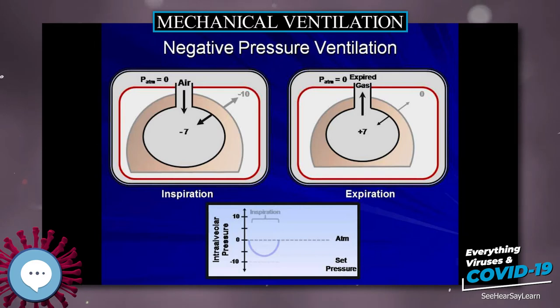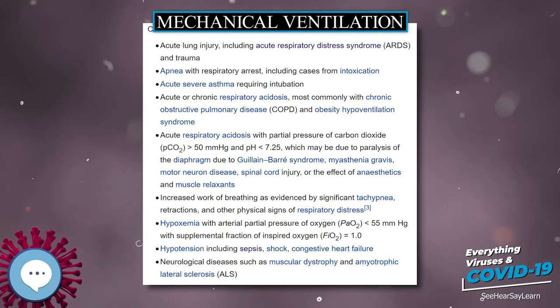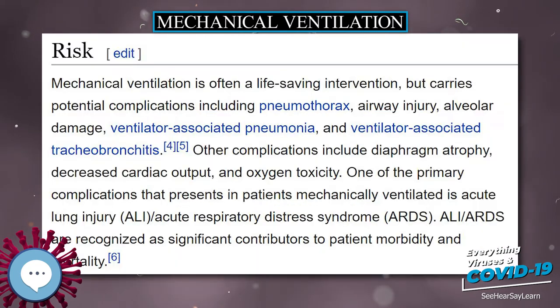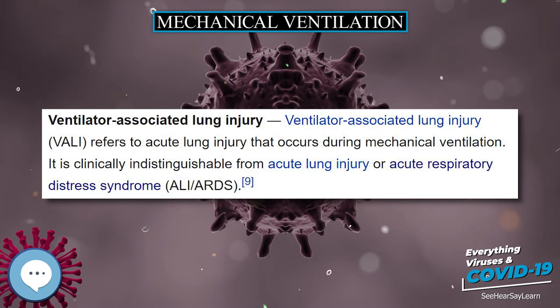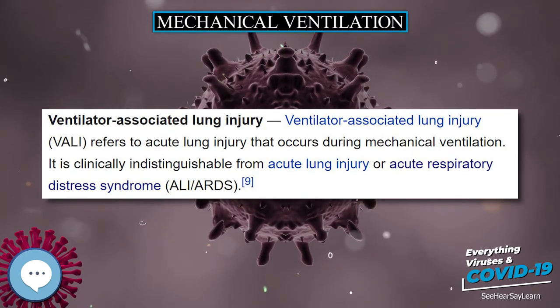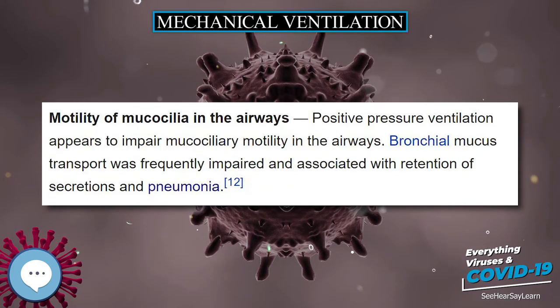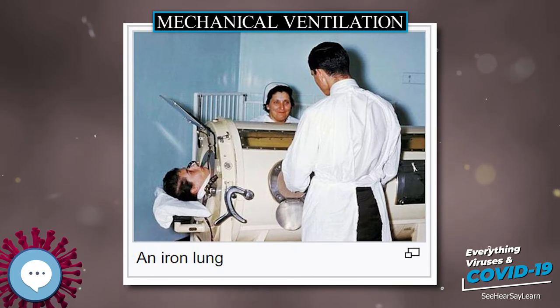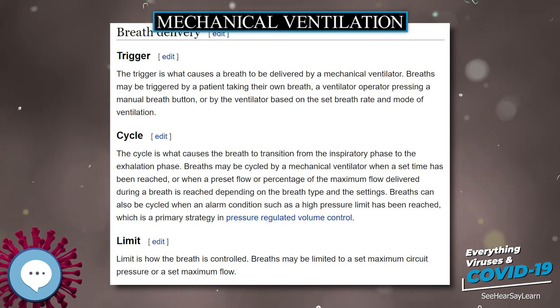While the exchange of oxygen and carbon dioxide between the bloodstream and the pulmonary air space works by diffusion and requires no external work, air must be moved into and out of the lungs to make it available to the gas exchange process. In spontaneous breathing, a negative pressure is created in the pleural cavity by the muscles of respiration, and the resulting gradient between the atmospheric pressure and the pressure inside the thorax generates a flow of air. In the iron lung, by means of a pump, air is withdrawn mechanically to produce a vacuum inside the tank, creating negative pressure. This leads to expansion of the chest, which causes a decrease in intrapulmonary pressure and increases flow of ambient air into the lungs. As the vacuum is released, the pressure inside the tank equalizes to that of the ambient pressure, and the elastic coil of the chest and lungs leads to passive exhalation.